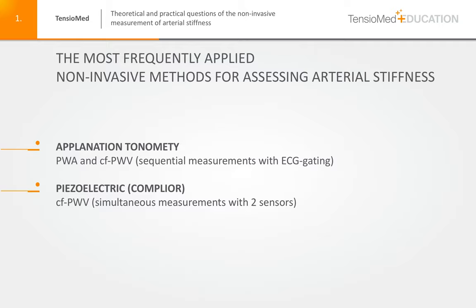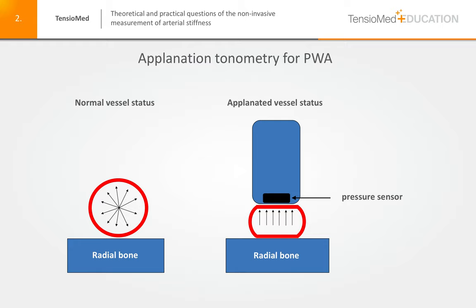Formerly, the most frequently used non-invasive methods for assessing arterial stiffness were aplanation tonometry and the piezoelectric method. Using aplanation tonometry for pulse wave analysis, we have to diminish the diameter of the artery, pushing the probe against the artery to arrange the pressure vectors towards the sensor and to obtain pressure curves.